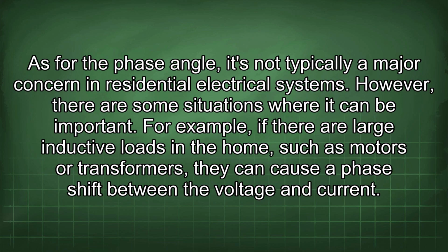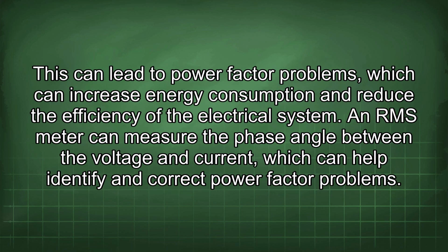As for the phase angle, it's not typically a major concern in residential electrical systems. However, there are some situations where it can be important. For example, if there are large inductive loads in the home, such as motors or transformers, they can cause a phase shift between the voltage and current. This can lead to power factor problems, which can increase energy consumption and reduce the efficiency of the electrical system. An RMS meter can measure the phase angle between the voltage and current, which can help identify and correct power factor problems.